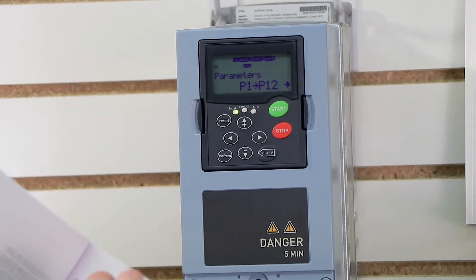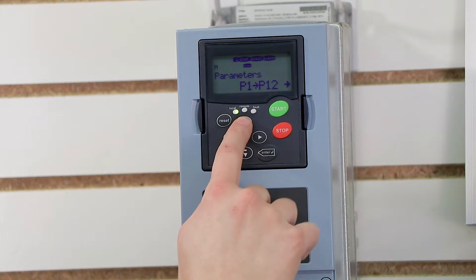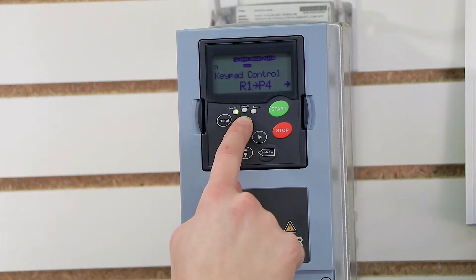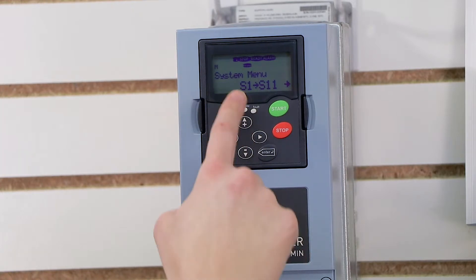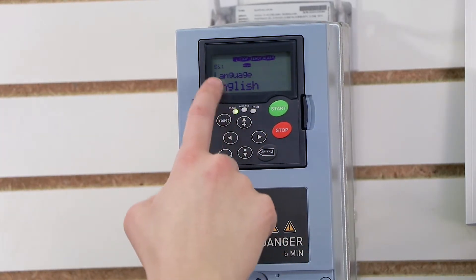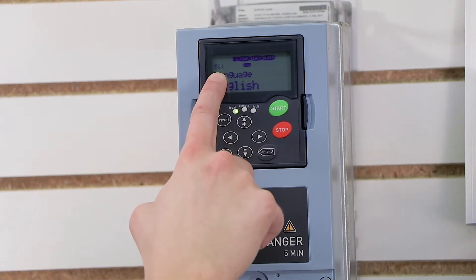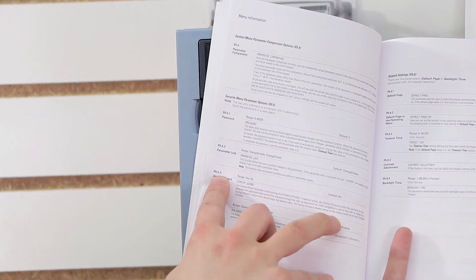I'm going to start at M5, which is my system menu. I'll press the up arrow key — M2, M3, M4, M5. Then I'll press right, and that M changed into an S5. So now I'm at S5.1. The parameter I'm looking for is 5.5.3, so I'll press up again: 5.2, 5.3, 5.4, and 5.5. Now I'm at S5.5.